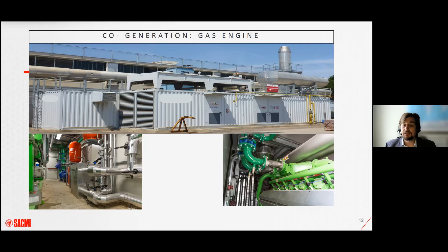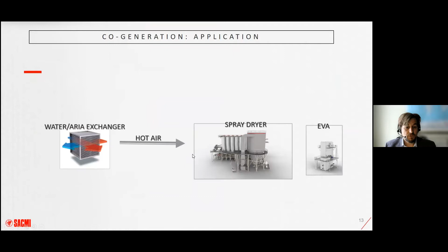So we see the latest technology introduced in the ceramic industry that involves the recovery of heat from the engine cooling water and in general from thermal waste, that is, excess thermal energy generated at low temperature. First, by an exchanger, it's possible to supply hot air for the combustion line to the spray dryer, heat generator, or to feed the vertical dryer.